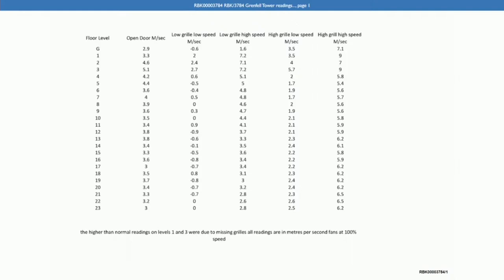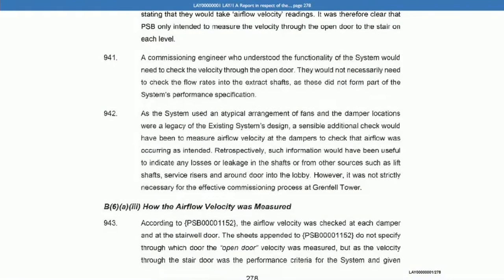Yeah, can we just look at what you say at page 278, paragraph 942, please, of your report? You say, as the system used an atypical arrangement of fans and the damper locations were a legacy of the existing system's design, a sensible additional check would have been to measure airflow velocity at the dampers to check that airflow was occurring as intended. I think that's one of the things I was thinking of, about it not having been done. What are you referring to there about the sensible additional check? Well, I think that measuring the airflow at each of the dampers is a sensible additional check. Right. Yeah. So not just one airflow measurement...